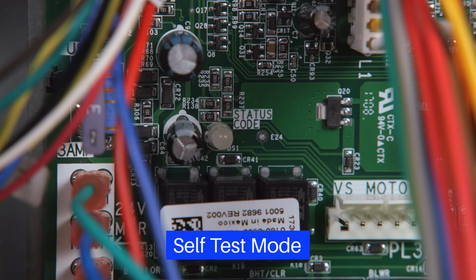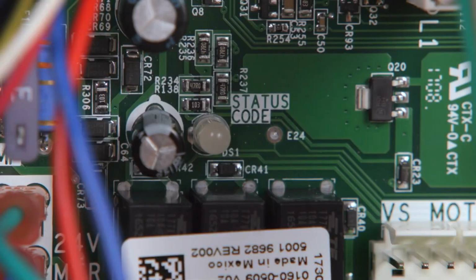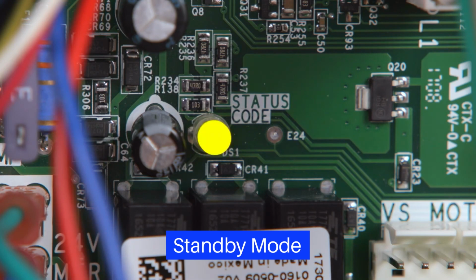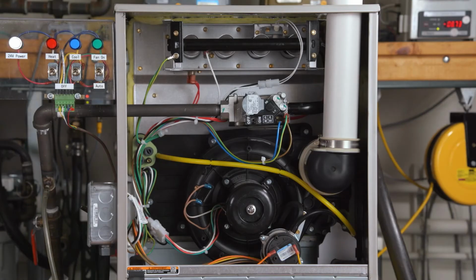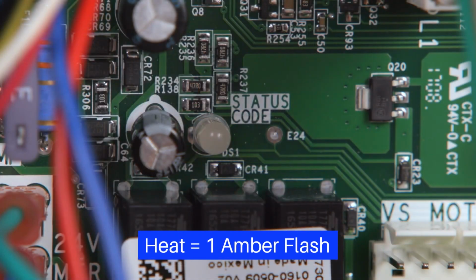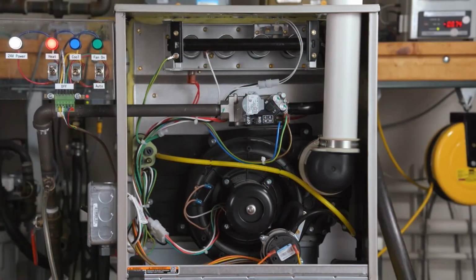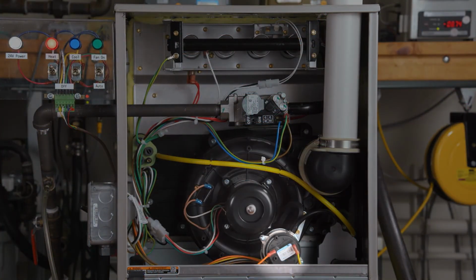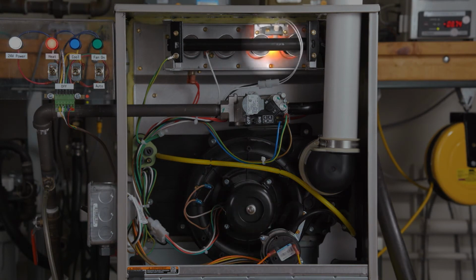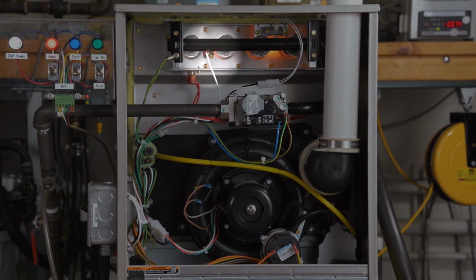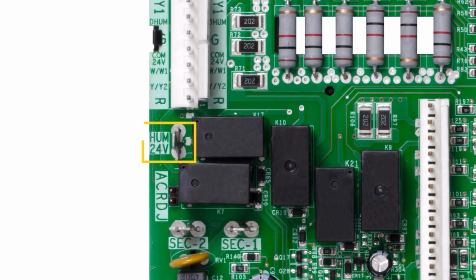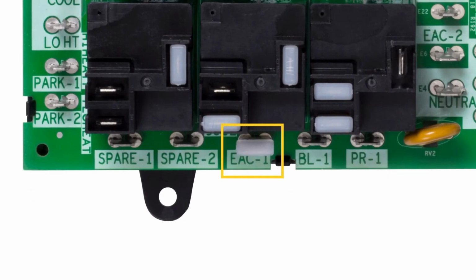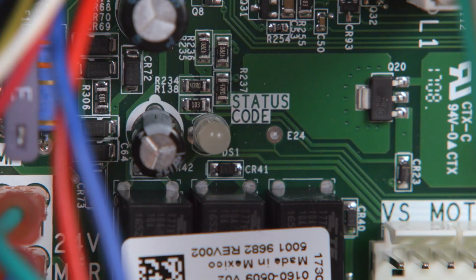During self-test mode, the LED will slowly flash between green, amber, and red while the control runs the inducer motor, igniter, and blower motor through all available speeds. When self-test mode is complete, the control will enter standby mode and display a green LED. To verify proper ignition, make a call for heat. The LED will slowly flash a single amber flash. The normal sequence of operation is inducer blower, pressure switch actuation, igniter warm-up, gas valve, flame sensor, blower, humidifier, and EAC if so equipped. The tricolor LED conveys system status and fault codes.